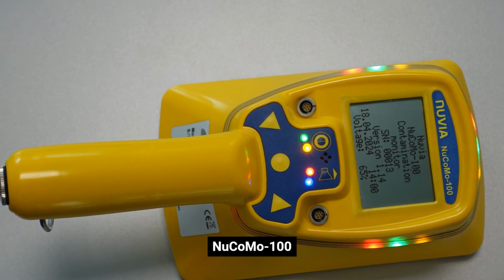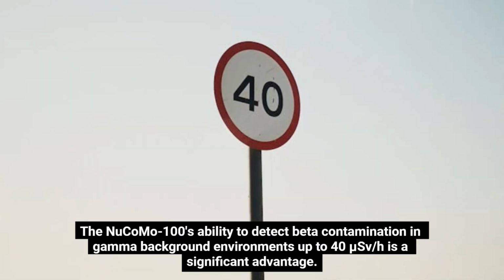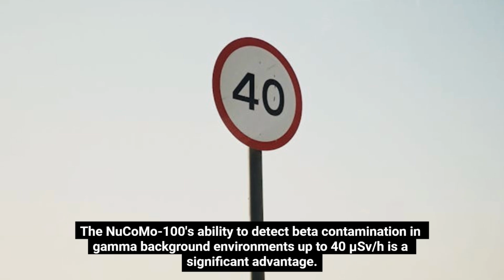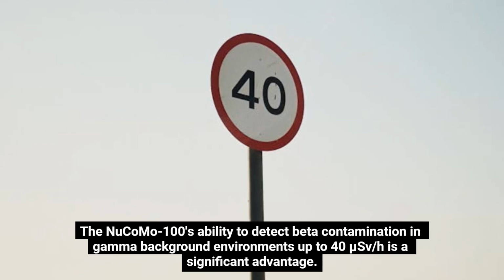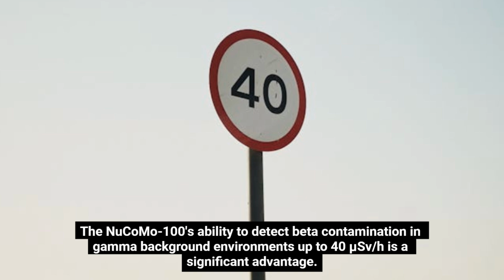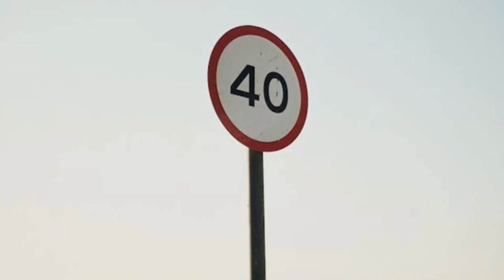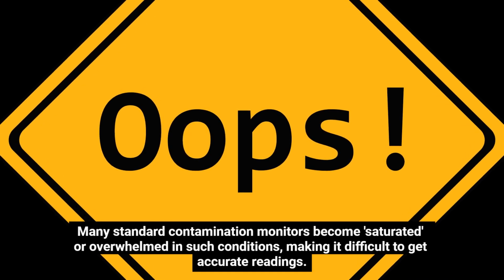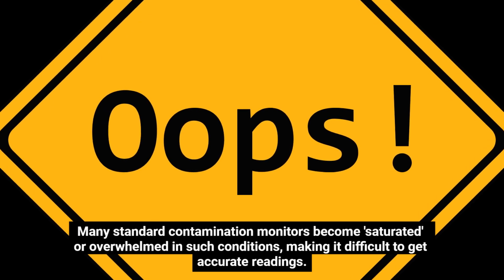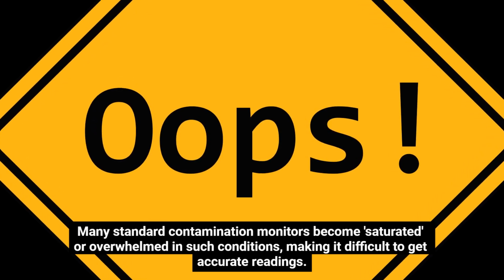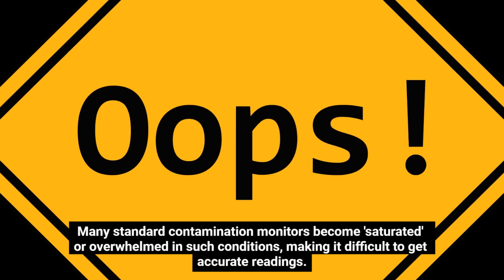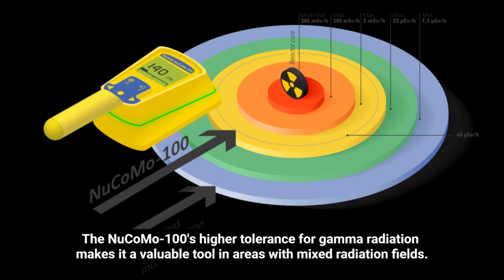NuCoMo 100. The NuCoMo 100's ability to detect beta contamination in gamma background environments up to 40 microsieverts per hour is a significant advantage. Many standard contamination monitors become saturated or overwhelmed in such conditions, making it difficult to get accurate readings. The NuCoMo 100's higher tolerance for gamma radiation makes it a valuable tool in areas with mixed radiation fields.